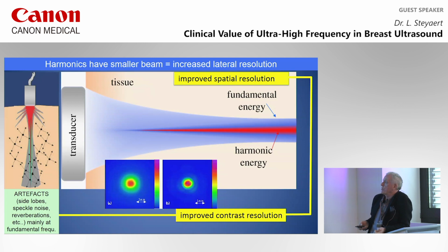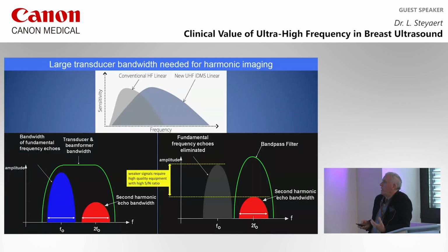What is the advantage of it? The harmonics have a much smaller beam, so we have an increased lateral resolution in our image. So higher frequencies, better resolution; harmonics, better lateral resolution of the image. On the other hand, we have an improved contrast resolution because we get rid of side lobe, speckle noise, and things like this, reverberations. They are situated on the fundamental frequencies, and they are filtered away with our system.